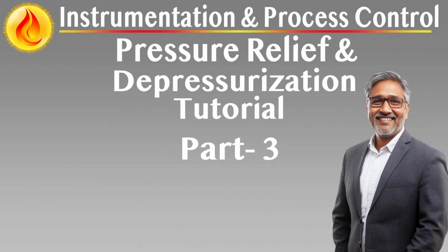Low temperature evaluation. Emergency depressurization leads to rapid expansion and vaporization of fluids, often resulting in significant temperature drops. These low temperatures can cause materials to become brittle, potentially compromising the structural integrity of equipment and piping. Design considerations include evaluating minimum metal temperatures expected upstream and downstream of the depressurization valves during full venting. Select materials of construction that remain ductile at the lowest anticipated temperatures, particularly for equipment that may be repressurized soon after depressurization.